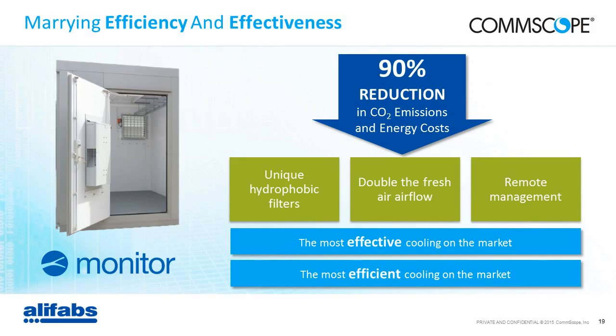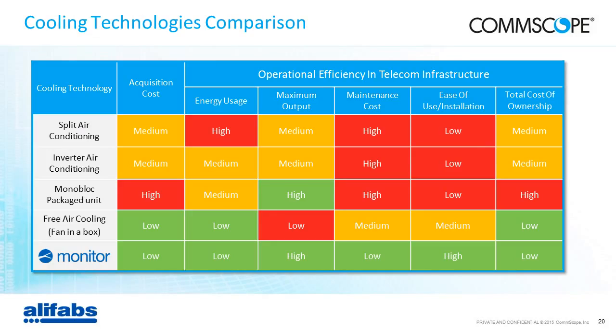But by making it the most effective free cooling system, it also makes it the most efficient system, because you've seen 3 slides ago that when the fan is running at lower partial load, its efficiency is at the maximum. So it's sort of a direct consequence of the effectiveness of the system. How does it compare overall with other cooling systems?